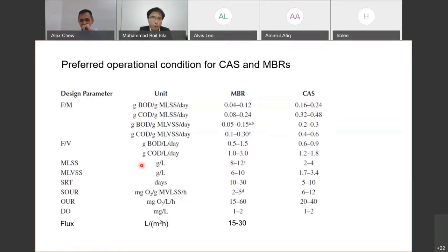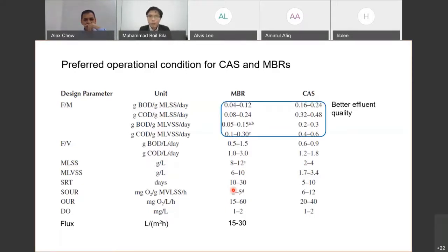Okay, for MLSS, for example, MLSS is basically mixed liquor suspended solids, basically the total sludge concentration. For MBR, we can go up to 10 to 12 grams per liter, while for the conventional activated sludge it is way lower, like a quarter of it. And you can also see different parameters. So if we look into these parameters, it also answers the question of why we have a better effluent quality in MBR.